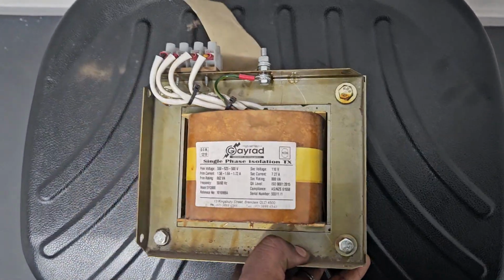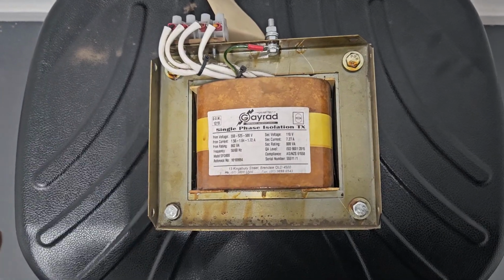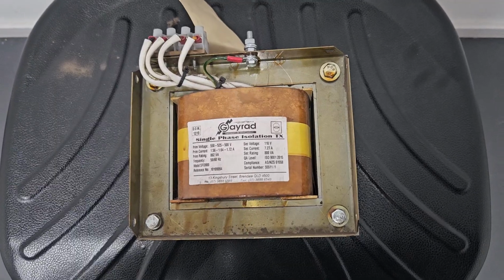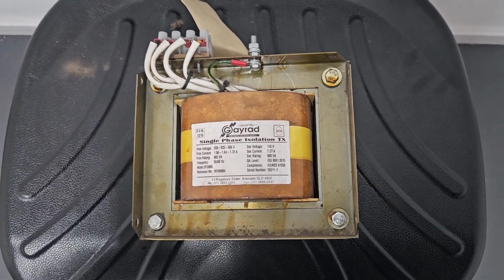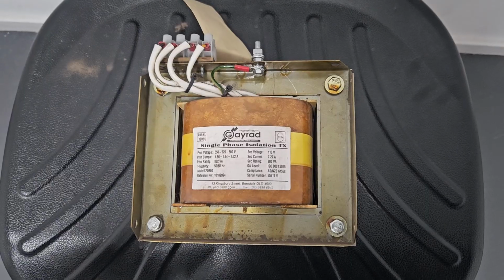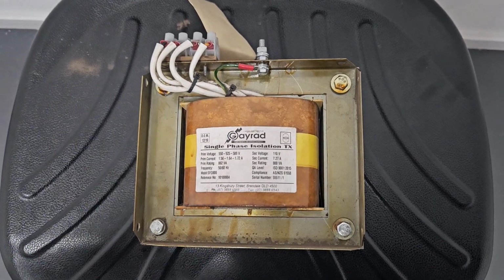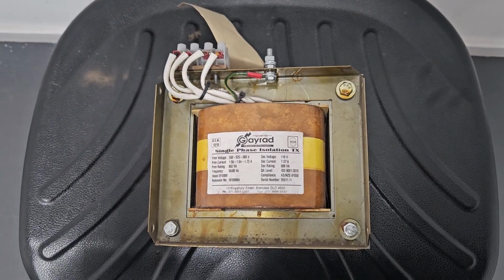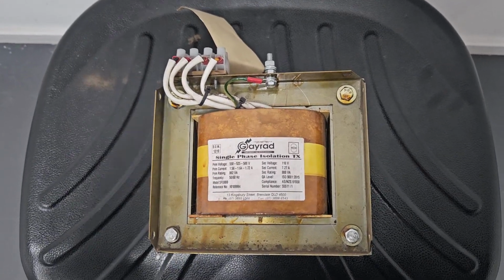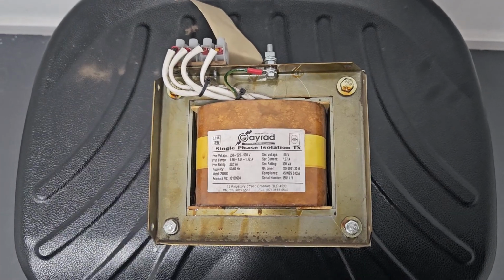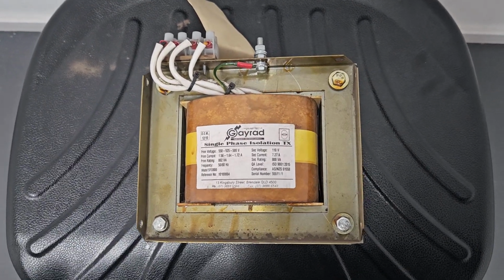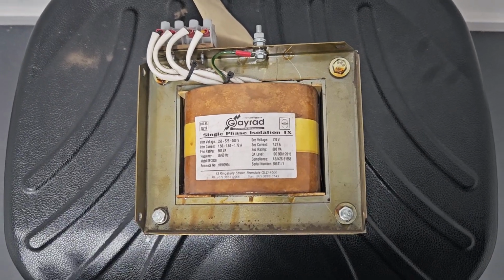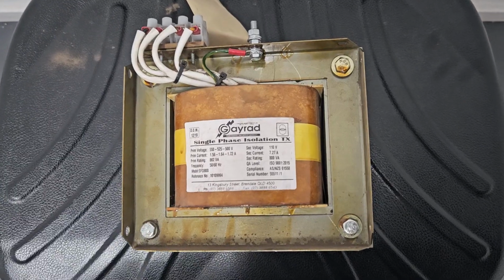In the second part of this video, we're going to cover a larger transformer. I just wanted us today to cover the basic components, which are the primary winding, the secondary winding, and the core. This transformer is going to warm up and heat up during transformation, but because it's a very small transformer, we just use air. Normally where it is installed, there will be a fan close to it to keep it cool. But when you get to larger transformers, you use other cooling methods like oil and larger fans. For smaller transformers, the natural cooling is just sufficient.